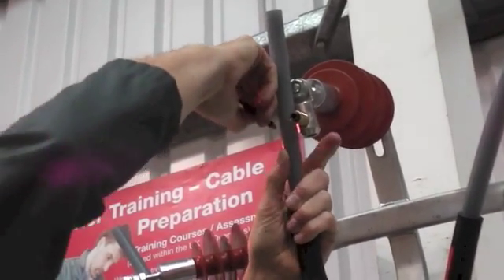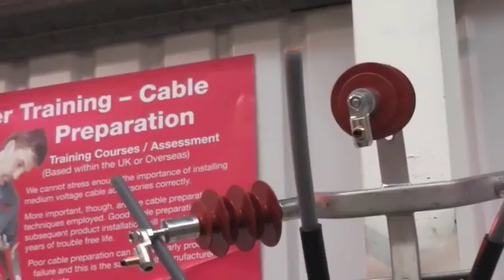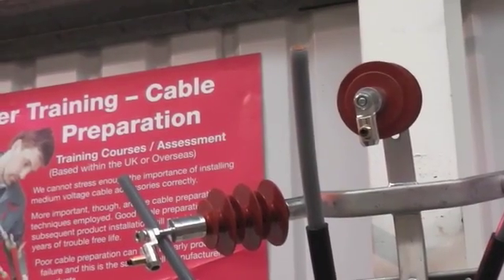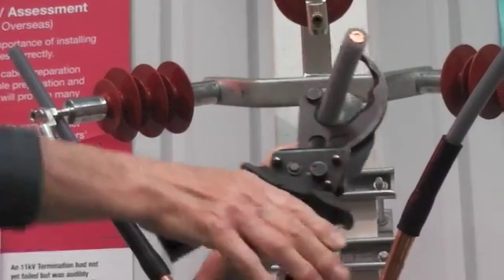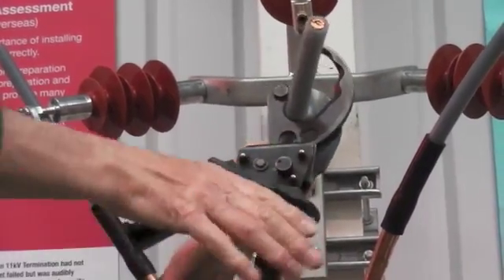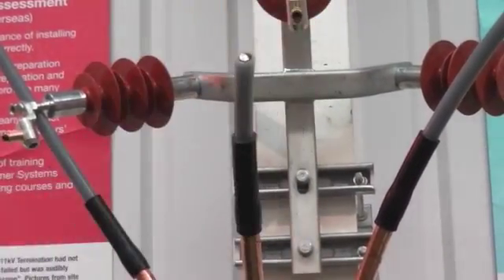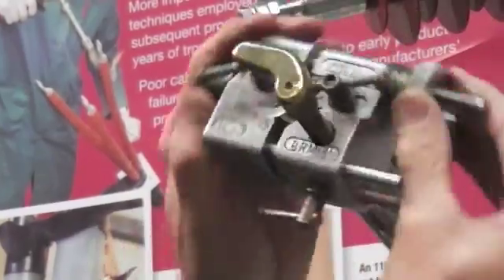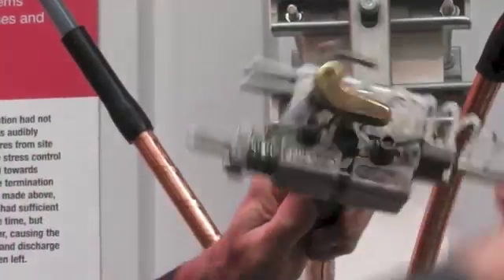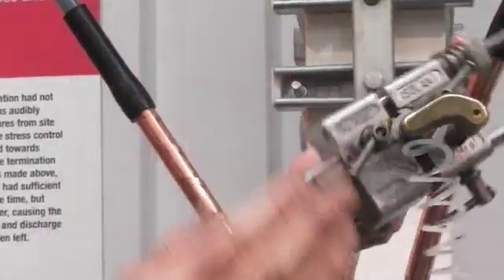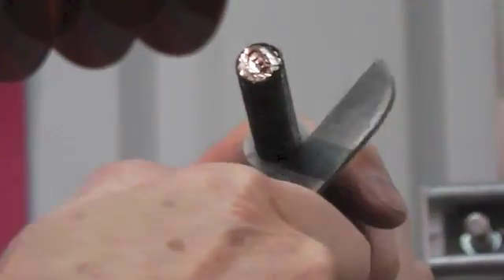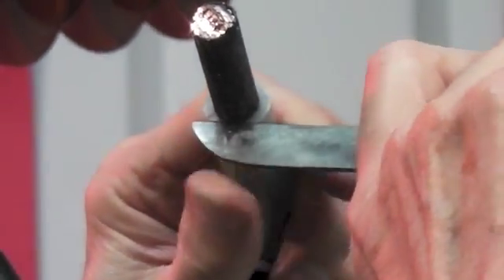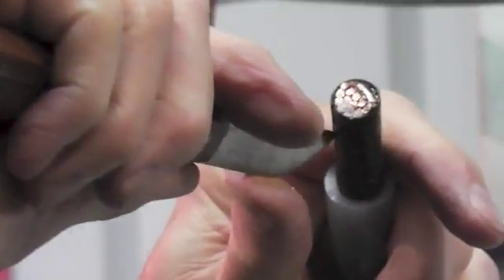Now fit the lugs, mark the holes, and cut to length. And we're showing an insulation removal tool here which will very quickly remove the insulation to the depth you set. Score the inner semi-conductive layer around the conductor and remove.